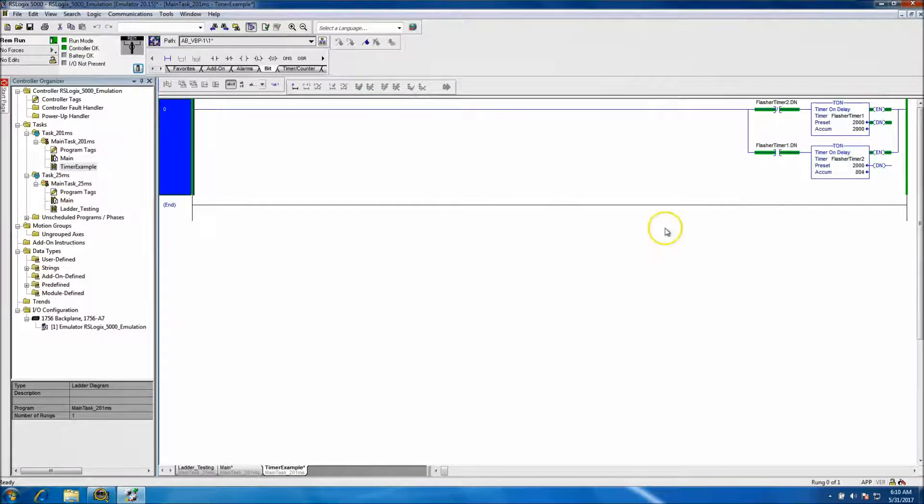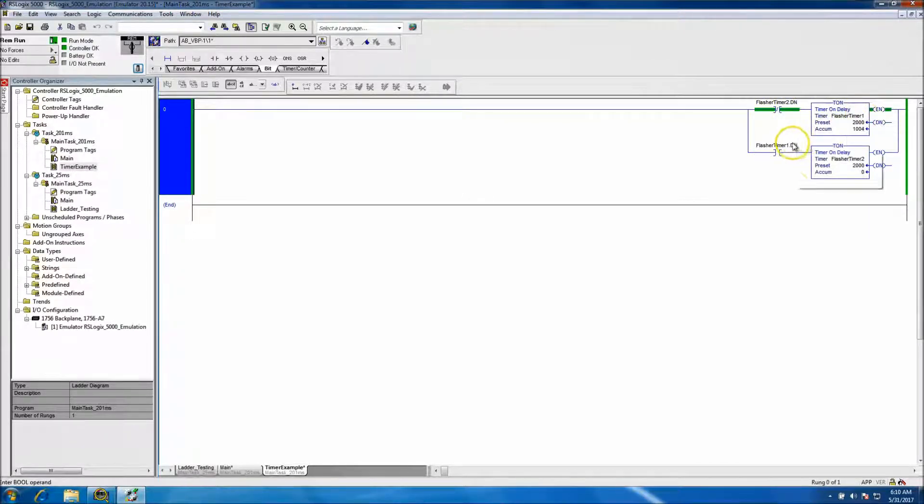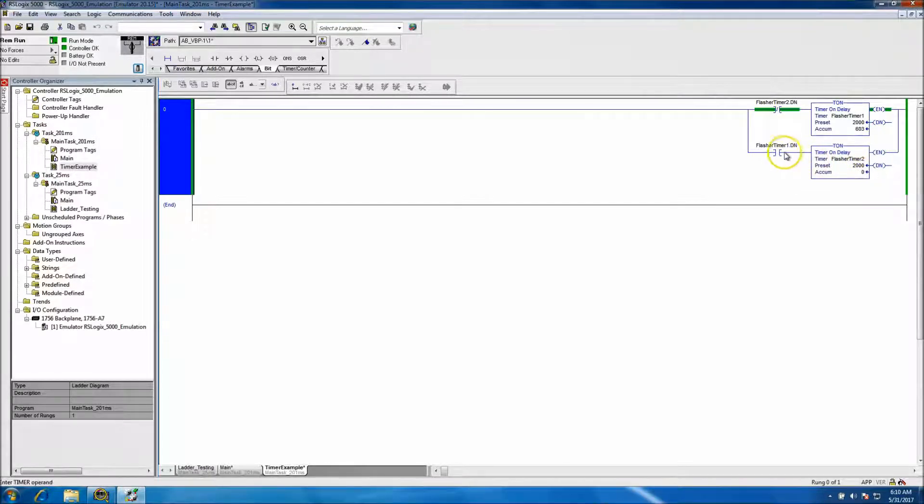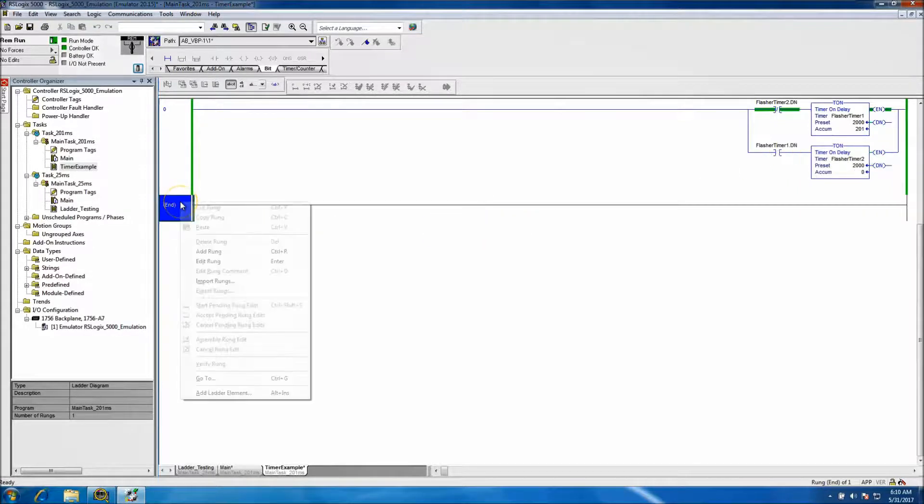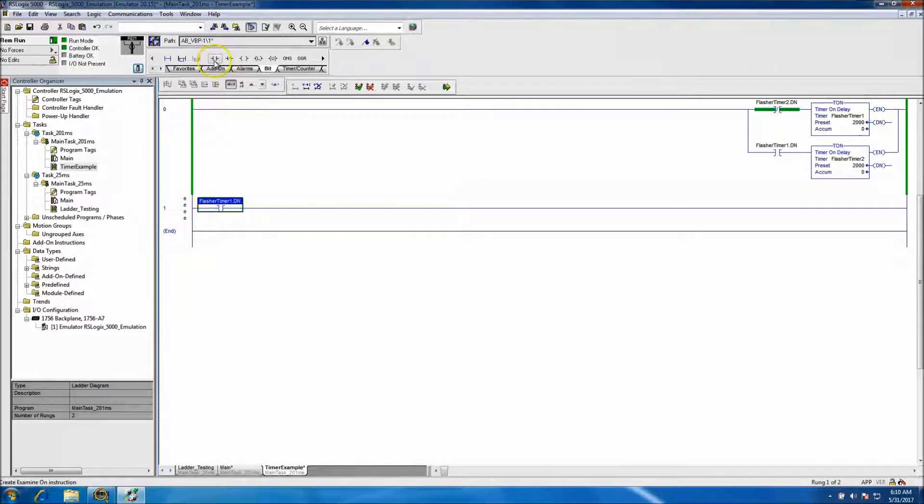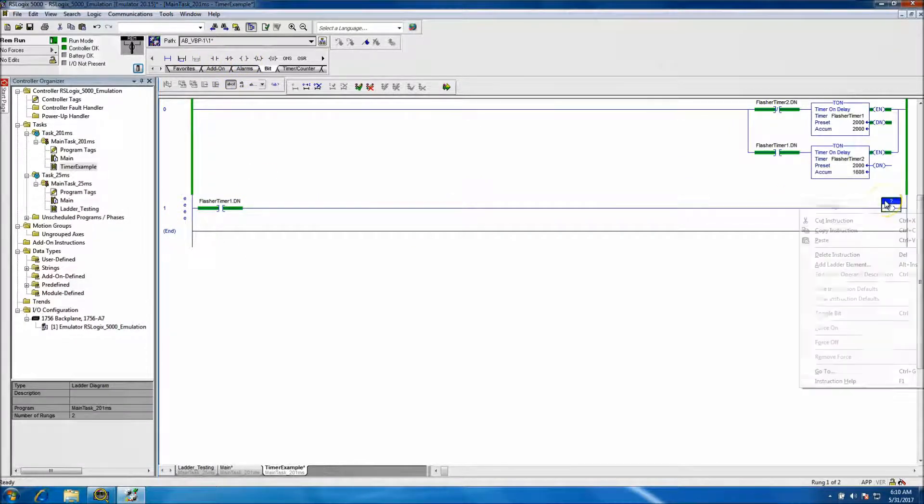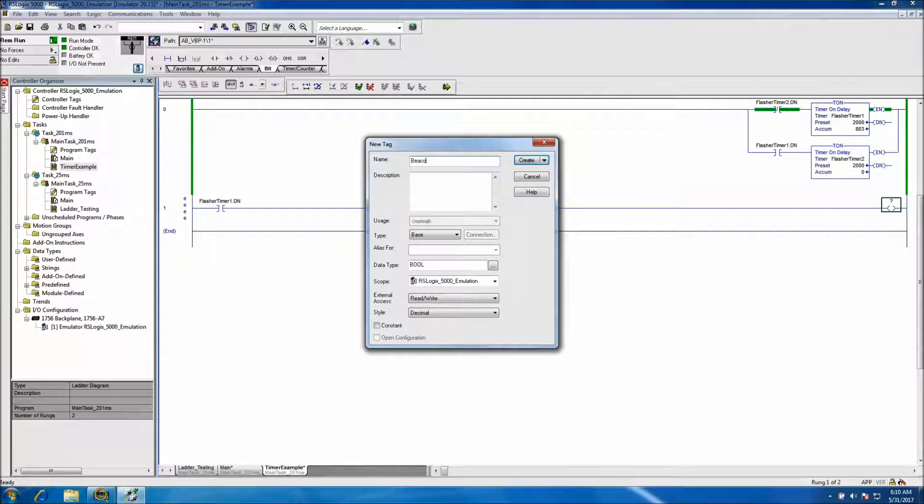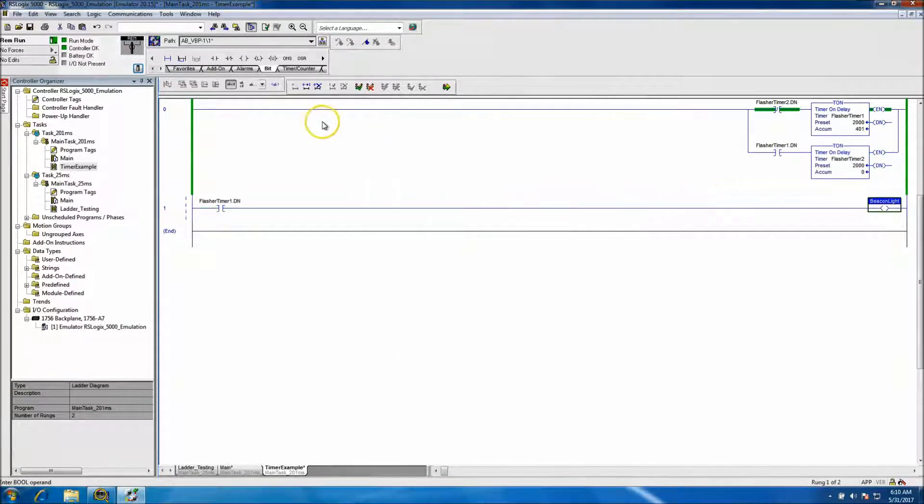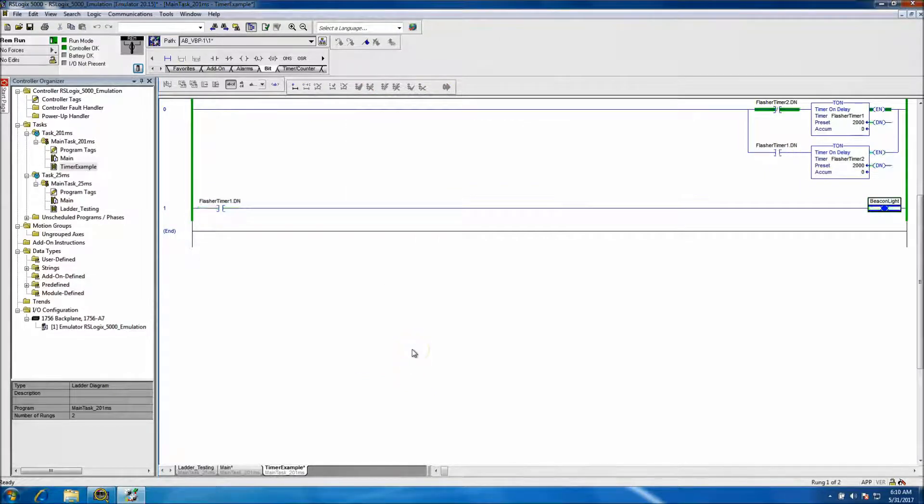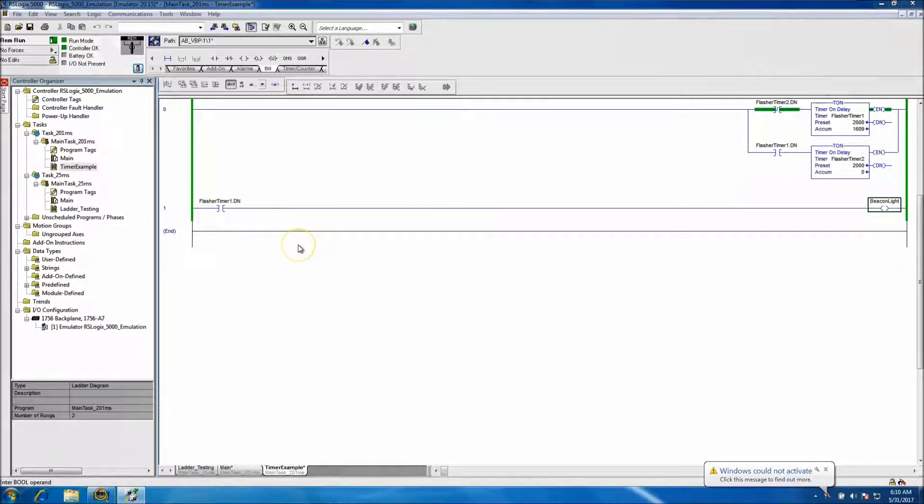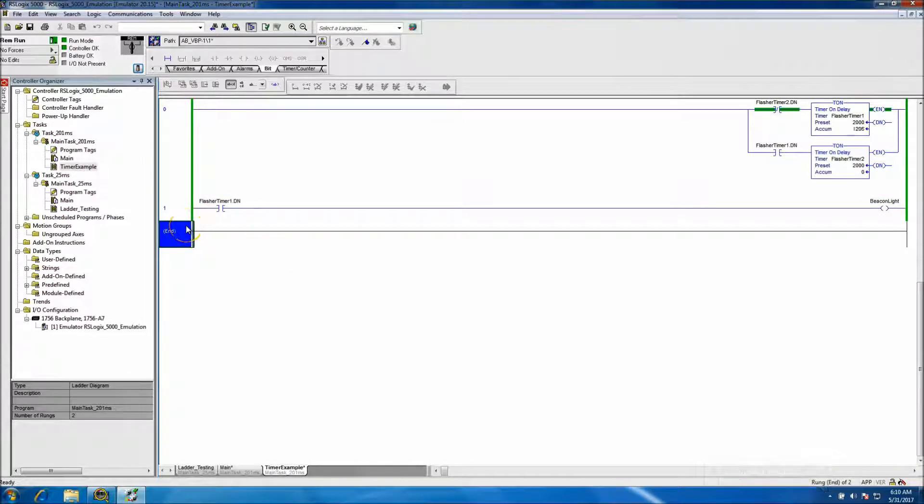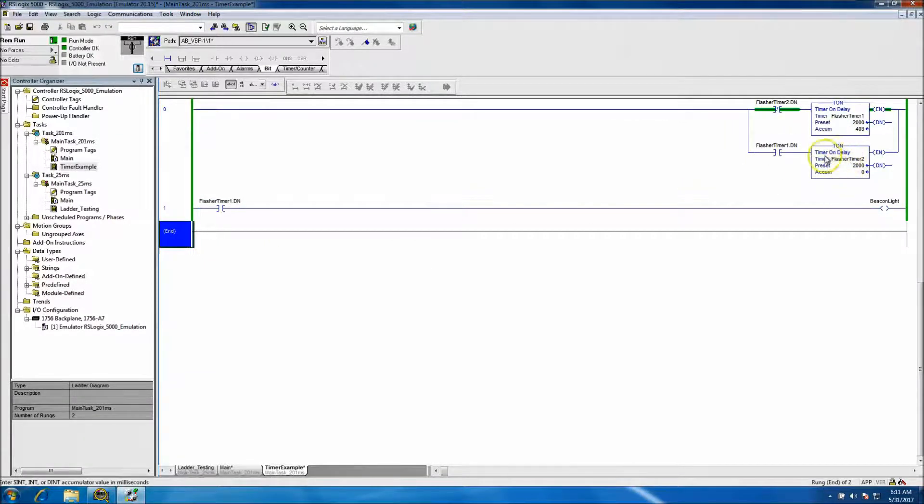Every time flasher timer one gets done, it indexes flasher timer two. You could use this bit right here to control something, like a beacon light. If you wanted to control the beacon light, it's pretty simple - on and off. If we had a fault or something, you could put it above that, and if the fault was active it would turn that on. That's basically a representation of a timer on.